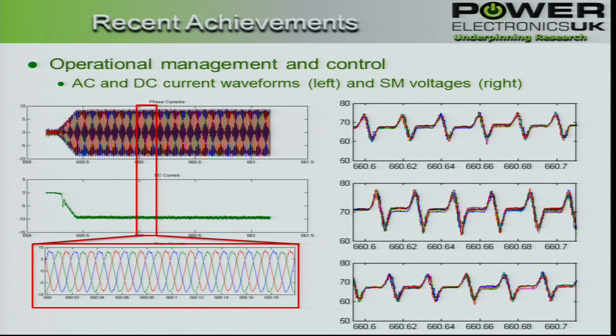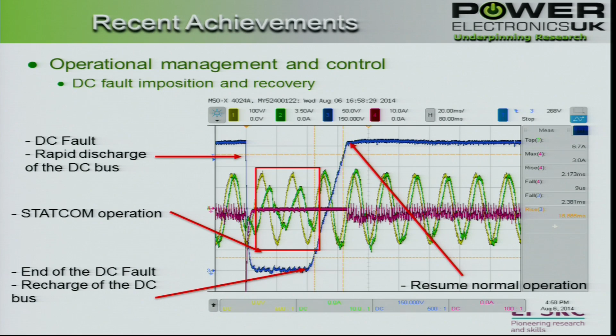Here's a result showing the system being put into fault and recovering from it. We've got the DC link voltage here in blue, a fault is imposed on it, and the converter under test continues to provide current in a controlled manner into the fault. When the fault is removed, the system recovers the DC link voltage. These results have just been achieved within the last few weeks, as the system's been commissioned and put into use. There's going to be much more work over the coming two years using this rig to explore the fault behavior further, and the behavior with condition monitoring techniques in the cells.